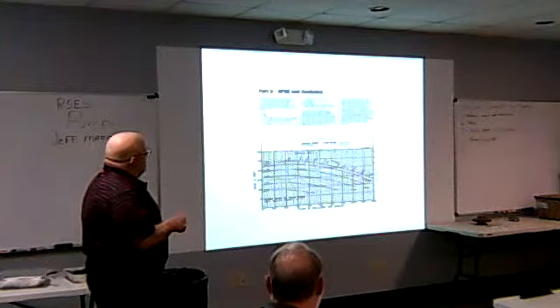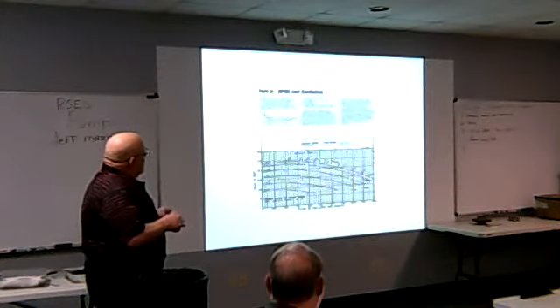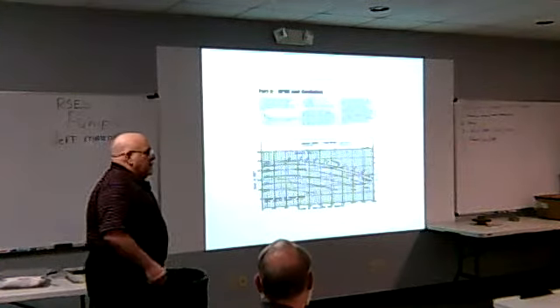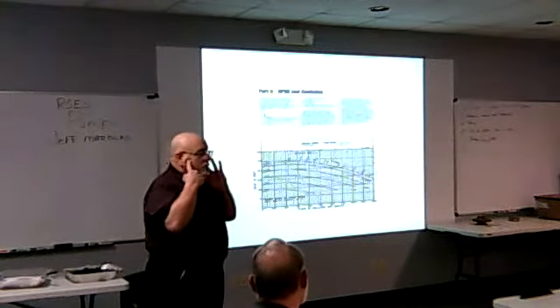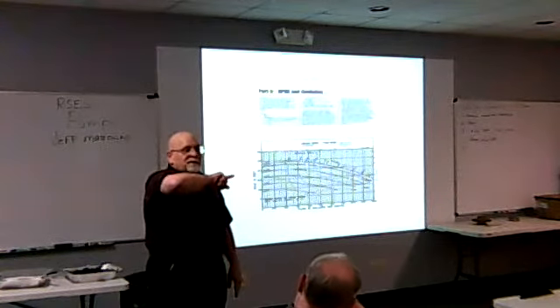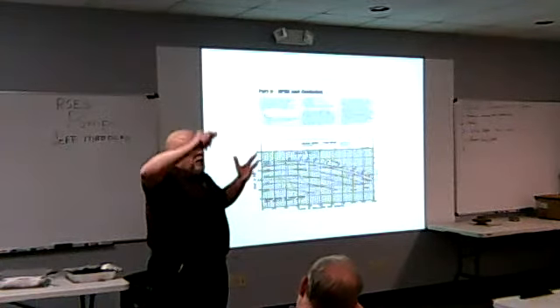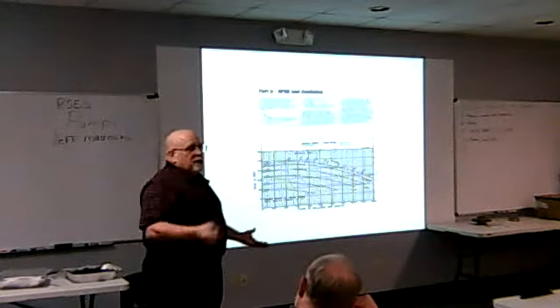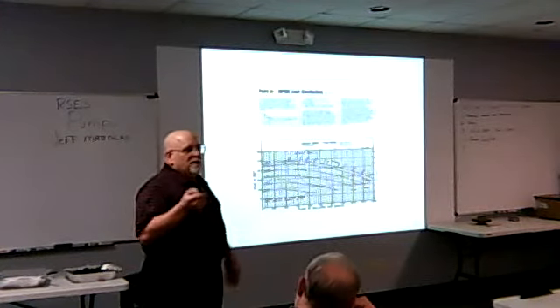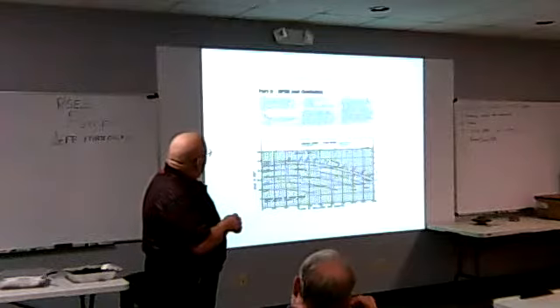I need 6 feet. Net positive suction head available is based on HA, which is atmospheric pressure, plus or minus system losses, plus or minus the vapor pressure of water. If you look at a steam table, 60-degree water, I might have 2 feet for the vaporization pressure. But when I get up to 212 degrees, what happens to that term? I'm getting closer and closer to boiling. Now we start at 32 feet from atmosphere. Well, in a chilled water system, I'm at 40. This term, 2, doesn't make much difference. Condensate system, I've got 32 here, minus 31, and I need 6.